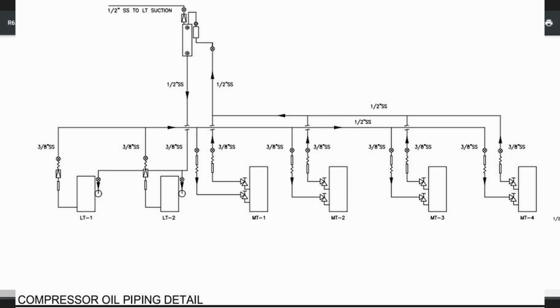And whatever oil is in there always settles to the bottom in an ammonia plant. And we have a little ball valve, a little 3/8 ball valve. We open that ball valve, and then that oil at, let's just say 25 pounds pressure, is pushed into the oil reservoir that feeds the low stage compressors. And we'll go over that in a minute. Okay. So at night, every night, we shut one evaporator off, drain the oil out. Now, we measured the oil loss on this system, and it's about 8 ounces a day.